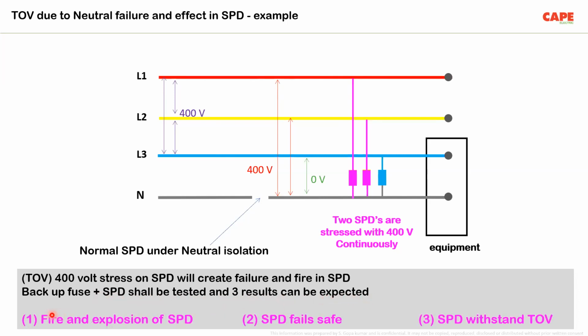The three results are: first, fire and explosion in an SPD. Second, the SPD may fail, but in a safe condition. The third is the SPD and the MCB will withstand. There are three results expected. The first result is dangerous because the SPD is catching fire, and these kinds of SPDs, the manufacturer is not supposed to sell in the market. Of course, which market is the question. Europe and America follow this very seriously. So the SPD manufacturer cannot sell these devices which create fire and explosion during a TOV. The SPDs should only fail safe or withstand during TOV. Only these two are supposed to be sold in the market.